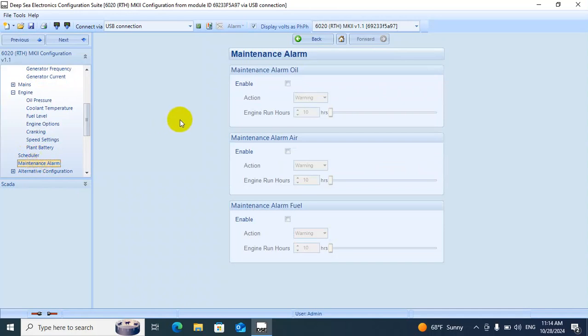This is for when we want a maintenance alarm, because sometimes we forget to check the generator. When maintenance is due and we have to change the oil, we tick this one, and the generator will give an alarm when it reaches the service time. This one is also about the air, and the maintenance alarm about the fuel. We are not touching this, we'll keep it like this.